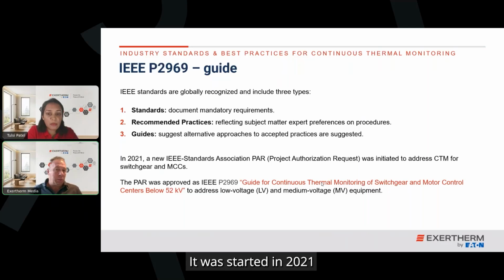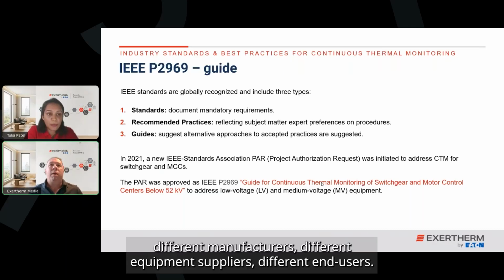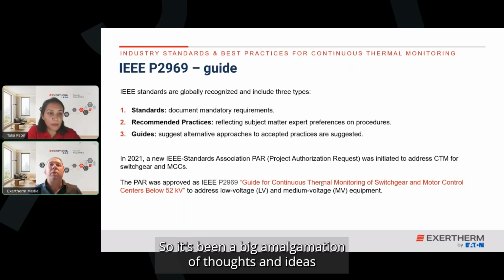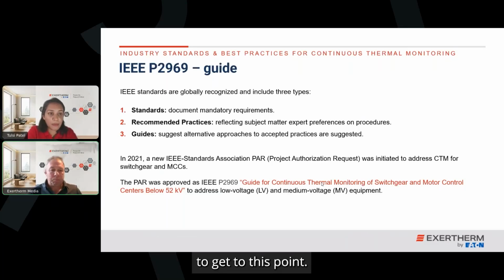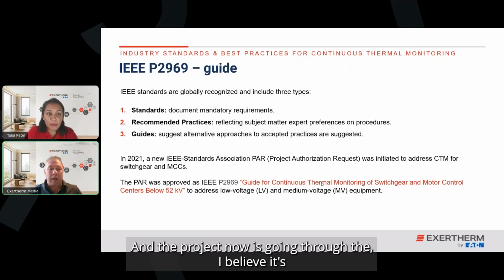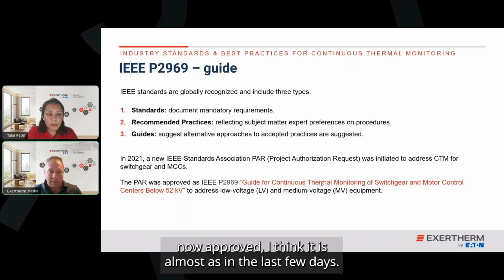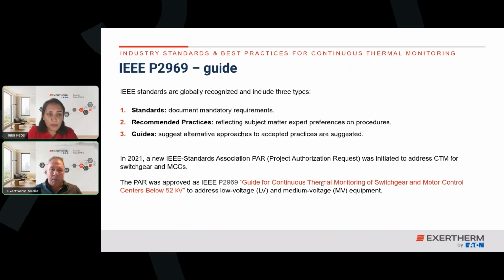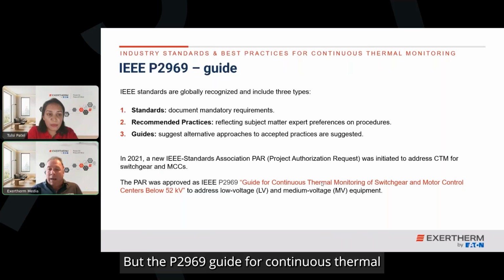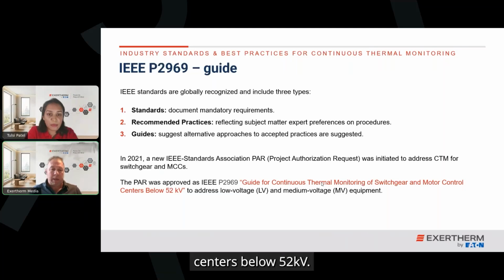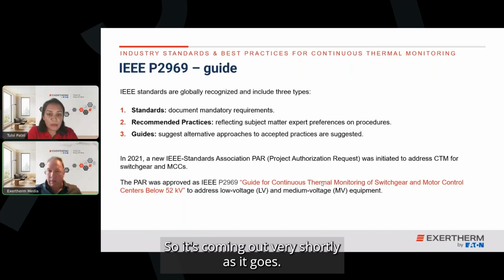It was started in 2021 by the Standards Association, and actually has been quite a large body of people from all walks of life, from all industries, from different OEMs, different manufacturers, different equipment suppliers, different end users. So it's been a big amalgamation of thoughts and ideas to get to this point. And the project now is going through, I believe it's now approved. In fact, I think it is almost as in the last few days, the P2969 Guide for Continuous Thermal Monitoring of Switchgear and Motor Control Centres below 52 kV. So it's coming out very shortly as a guide.